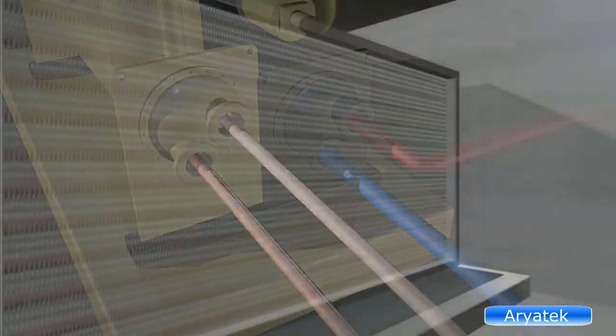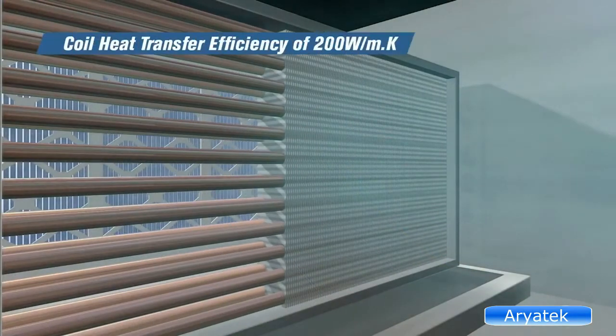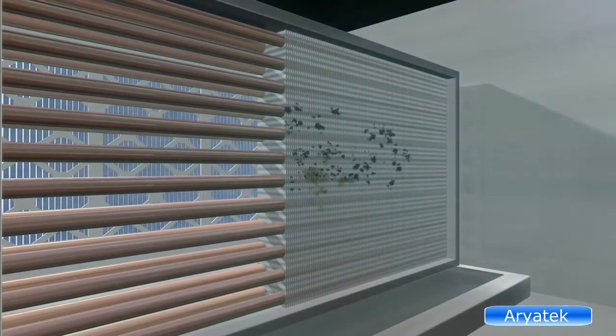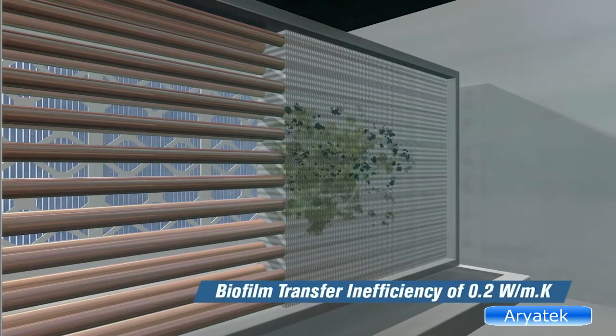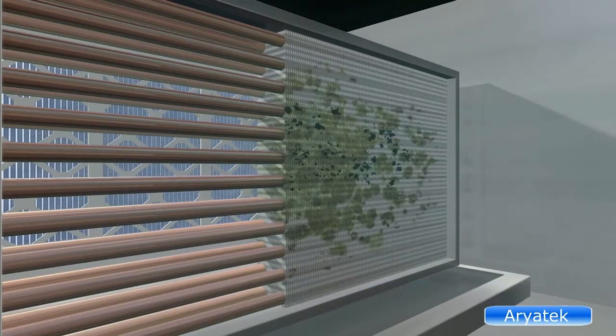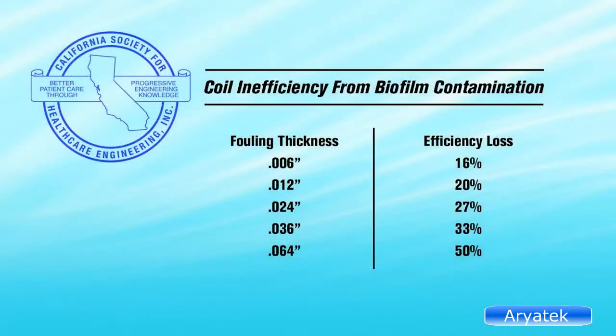The metal fins of the coil are typically made of aluminum that has a heat transfer efficiency of 200 watts per meter Kelvin, whereas the biofilm that often covers the fins may be 0.2 watts per meter Kelvin, or approximately 1,000 times less efficient. According to the California Society for Healthcare Engineering, it only requires a 0.15 millimeter fouling on the coil fins, 0.006 of an inch, to reduce the coil's efficiency by 16%.